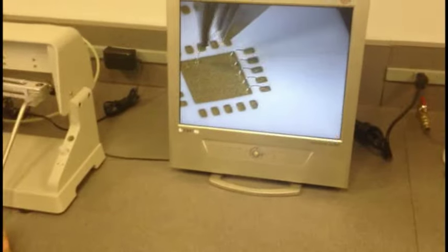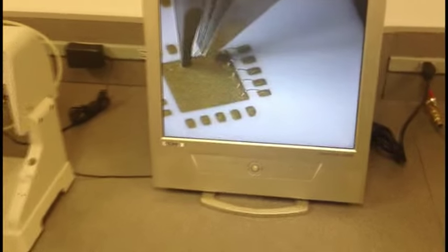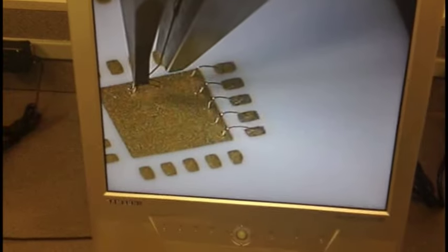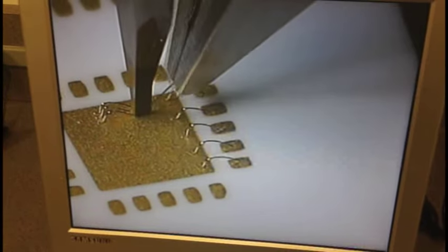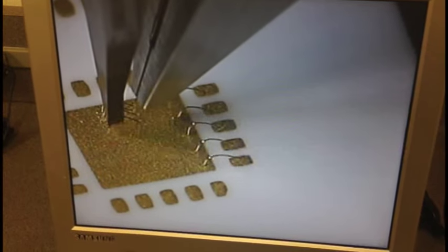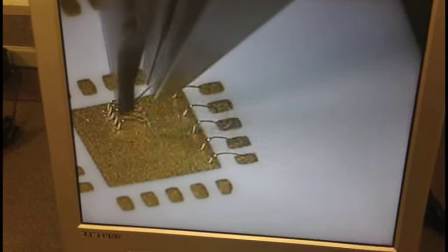Let's watch the machine in operation. The machine is set with a 45-degree wire feed. When the wire makes contact with the bond surface, the machine takes over, delivering the ultrasonic time and power along with the force.